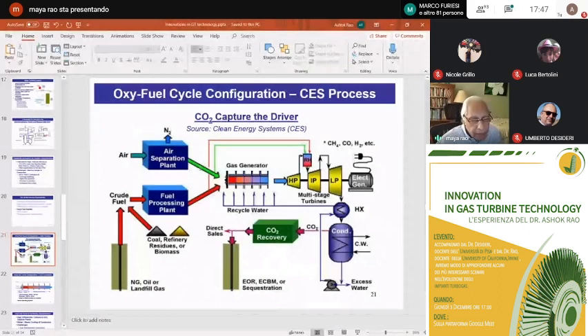If you have biomass or coal instead of natural gas, you'll have to convert that into a clean gas by gasification, where you have partial combustion of the fuel to make hydrogen and CO. That has to be cleaned up before introducing it into the combustor. So this section of the plant, the fuel processing plant, can be quite complex if you have dirty fuel.